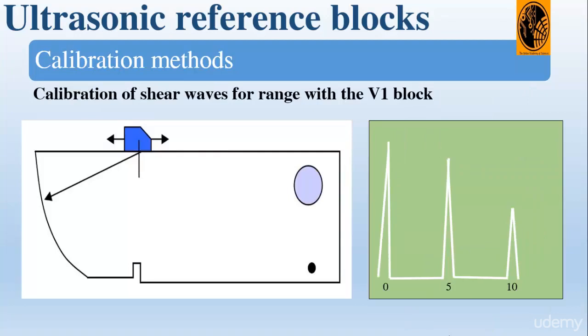Now we'll see the calibration of shear waves for range using the V1 block. By range in angle probe testing, we mean the distance a reflector is from the probe index. It is possible on some flaw detectors to calibrate the time base to 100 millimeter range from the V1 block; however, this involves the scale expansion setting, and not all equipment can do this. So we will confine ourselves to calibrating for 200 mm screen width.